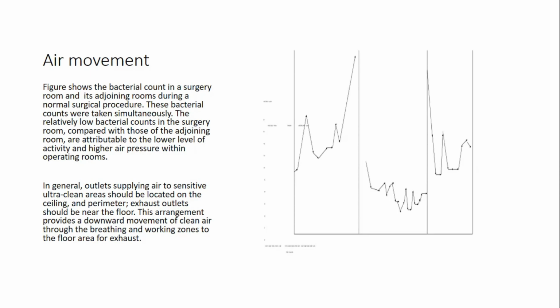So in this figure, the middle one is surgery one. You can see the bacterial count, which was live-measured. The bacterial count in a normal surgery room is relatively low compared to the other rooms. Why? Because of the higher air pressure within the operating room. That is the reason we normally use laminar flow in operation theaters, and we also use HEPA filters there. So that is the meaning of this air movement.